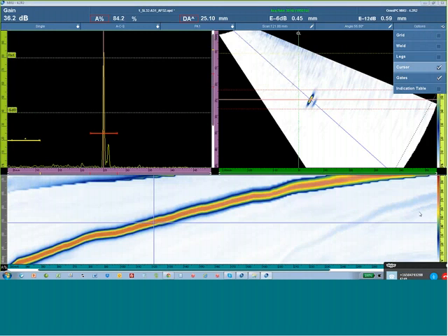Okay, on the clock, not on the encoder, we're taking a clock scan of a side drilled hole, exposing it from focal law or A-scan first all the way to A-scan last. And we're looking for several unique features that will expose the setup as either valid and exiting the wedge with appropriate beam acoustics or outside the range of the physics or the probe. This is a setup that we have calibrated for sensitivity that we can see in the C-scan, but we have not done anything to modify the wedge delay or made any tweaks. So we're coming right out of the calculator with regard to time of flight.